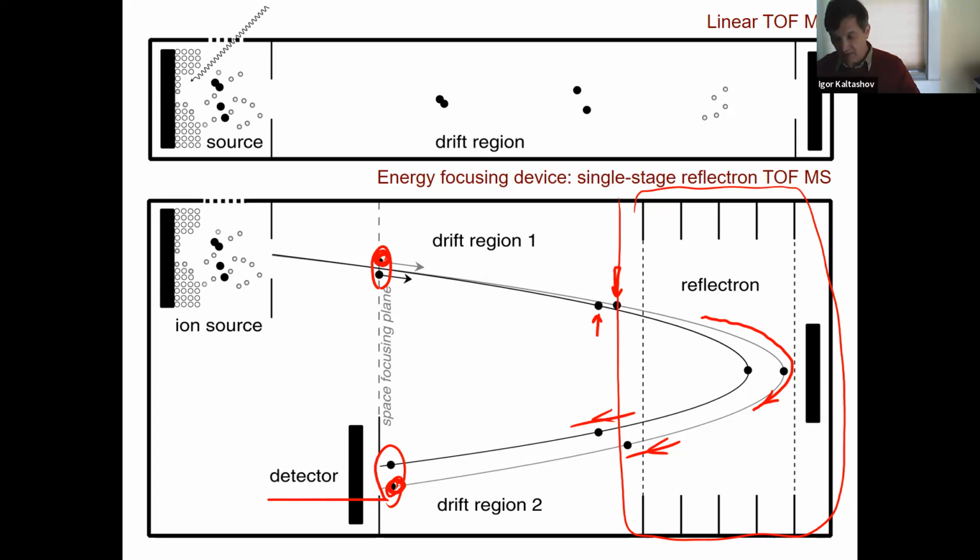And now instead of having a spread, you will have a collapse in this peak, and you would register both ions at exactly the same time. So that has resulted in a very significant improvement of resolution. So a very, very useful piece of hardware. And as I said, most modern time-of-flight instruments are equipped with that.